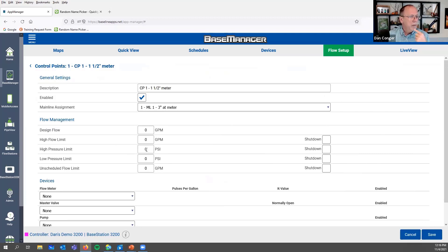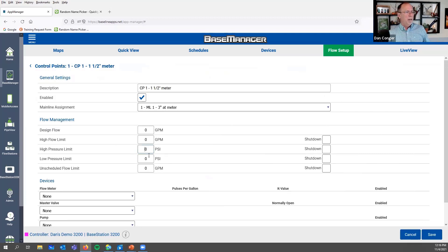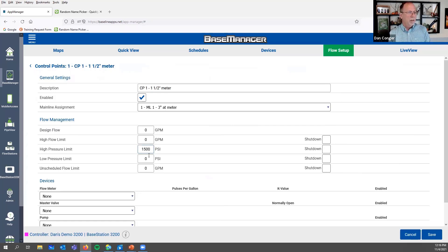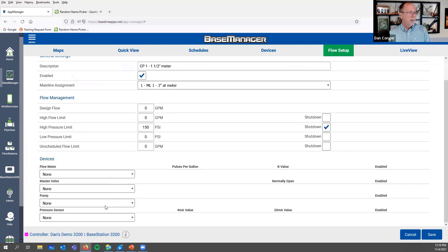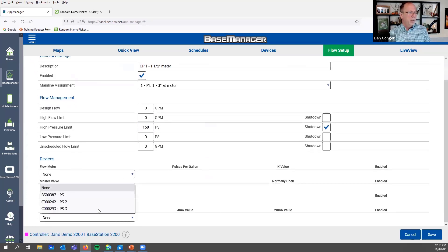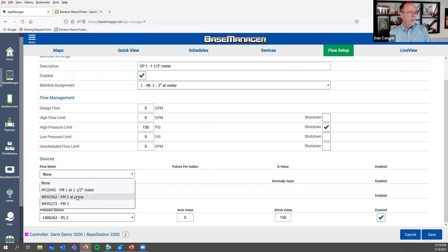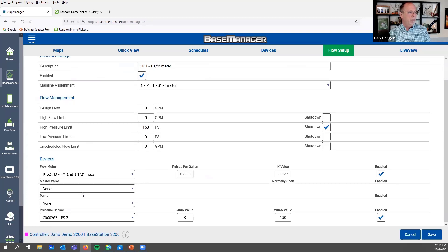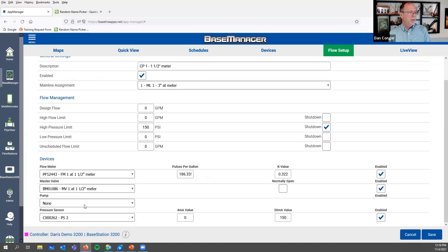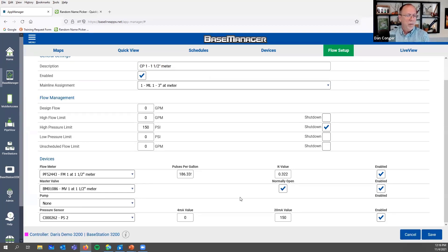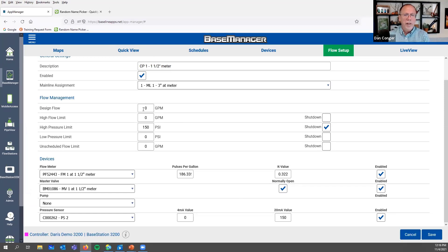In this case, I'm going to set a high pressure limit. And here I said 150 psi, not 1500 psi, and shut down. Now I got a problem here because I don't have my pressure sensor. Got to have my pressure sensor, got to have my flow meter and my master. I got to have the devices in there. And we said that was normally open, so I got to have that set up. I should also be setting up my flow data too, but this is the critical one—this is high pressure limit.